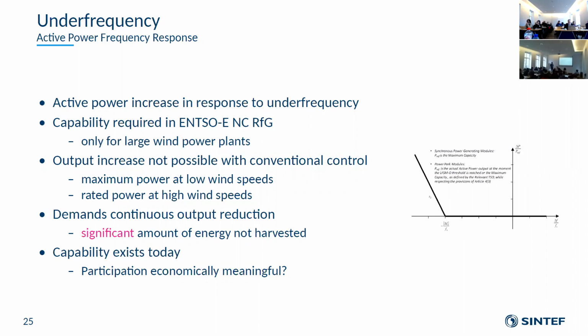But for wind power plants, you have to have this capability, and you need to decrease your output on a continuous basis, because normally this isn't possible. If you track maximum power, you're either at your limit or at the limit of what the actual wind speed gives you. So with normal wind power control, which maximizes energy extraction, you couldn't do this - you'd need to continuously curtail your output, and you lose a lot of power.